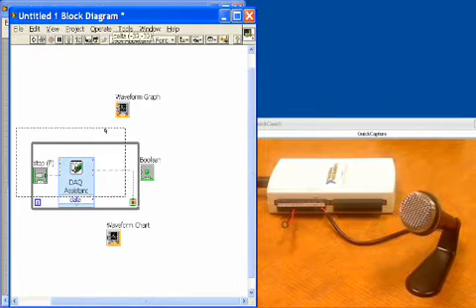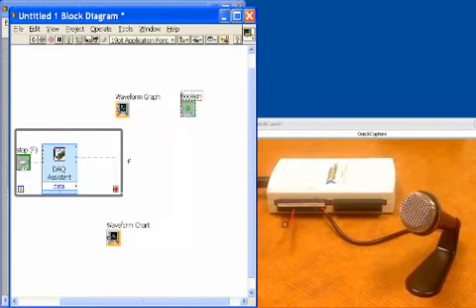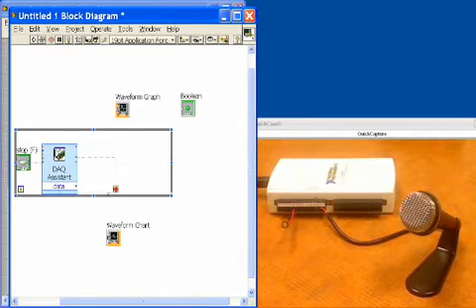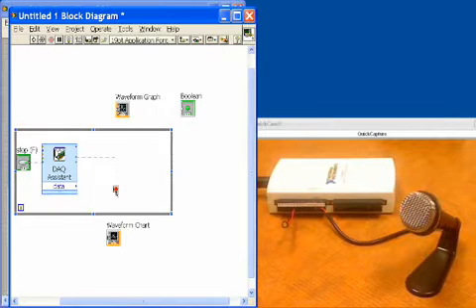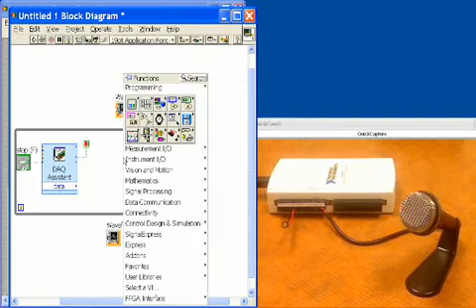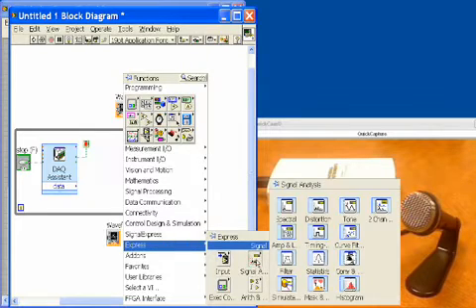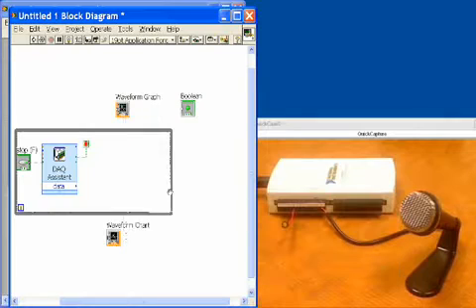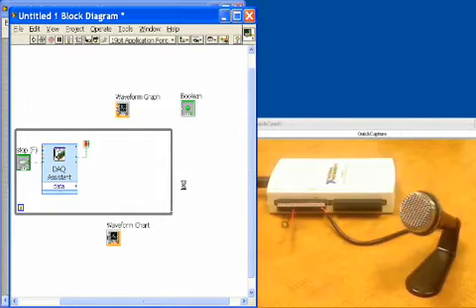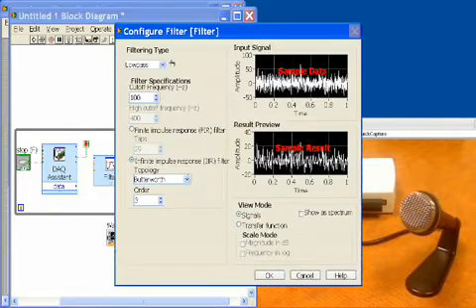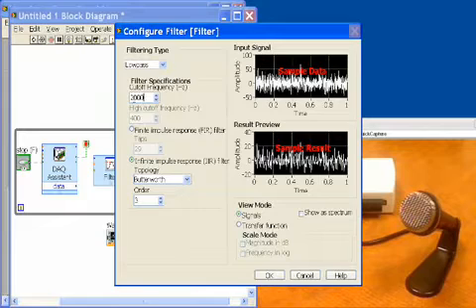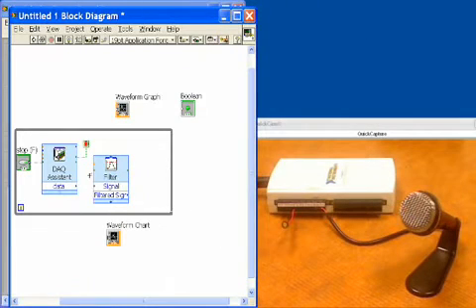The next thing we want to do is apply a filter because we know we're probably going to get some high frequency input that we don't want unless we intend it to come through. So we'll apply a filter to our data coming out of our analog input task. We'll go into our express functions, get our filter function, put it down and set it up. Inside our filter task we want a low pass option to filter everything from 2,000 hertz and up.